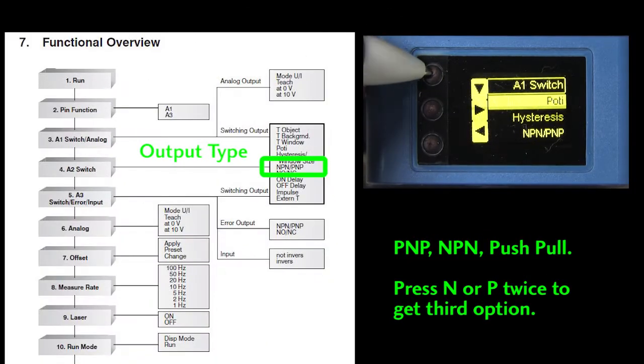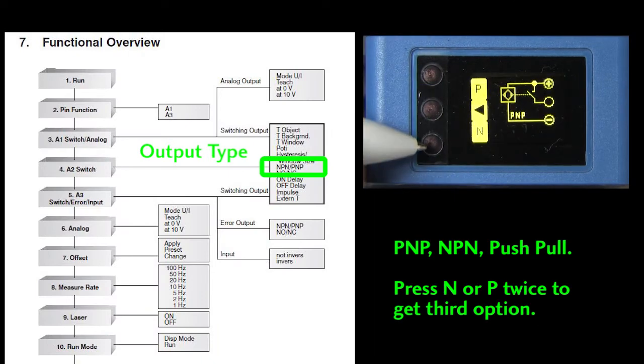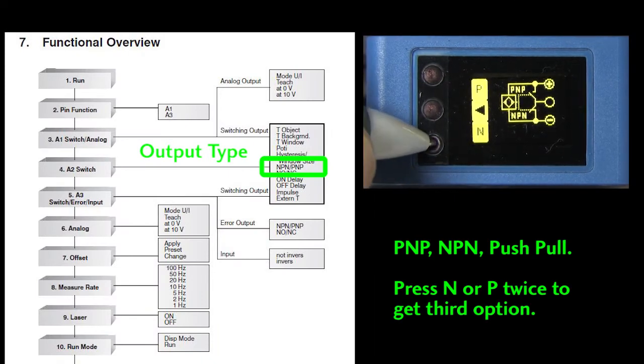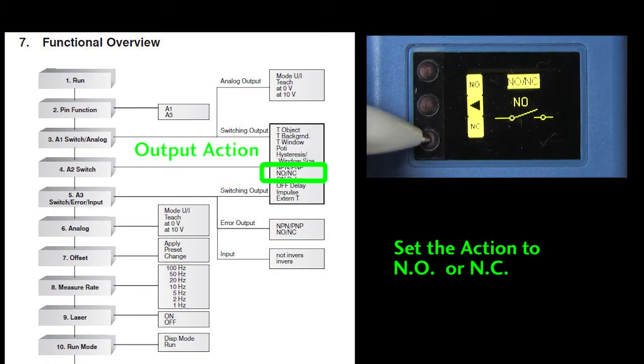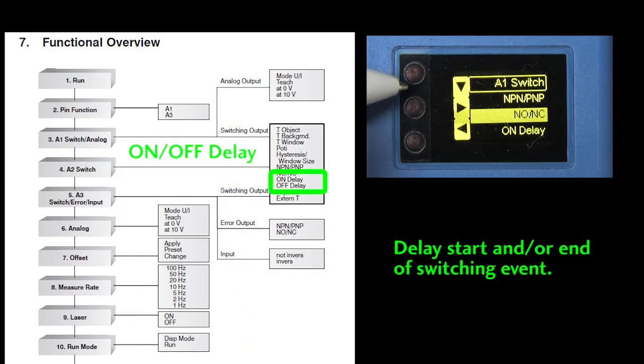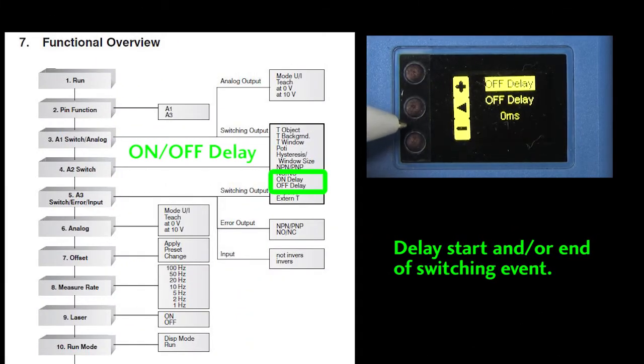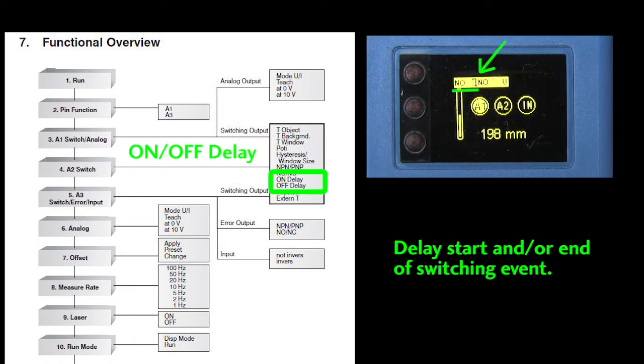This menu lets you set the output type. You can choose from these three options and look – it even shows you a diagram for each one. That's pretty cool. This menu lets you pick if the output should be normally open or normally closed. The on delay and off delay menus adjust how long the sensor waits to report the start or the end of an event. You can set the time from zero to 10 seconds. This little falling edge right here tells you that the off delay is enabled for this contact and this one tells you that the on delay is enabled. That's really handy.